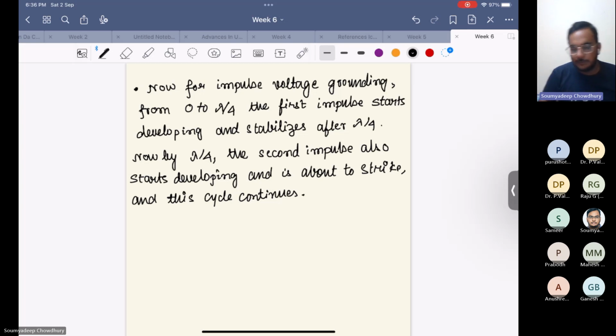However, for impulse voltage grounding, the signal frequency is very high, and for that this lambda by 4 will be very small. Before the first impulse wave stabilizes, the second impulse wave also starts developing and is about to strike, and this continues. After another lambda by 4, the third impulse starts and the second impulse wave gets stabilized. So there is an overlap of waveforms.